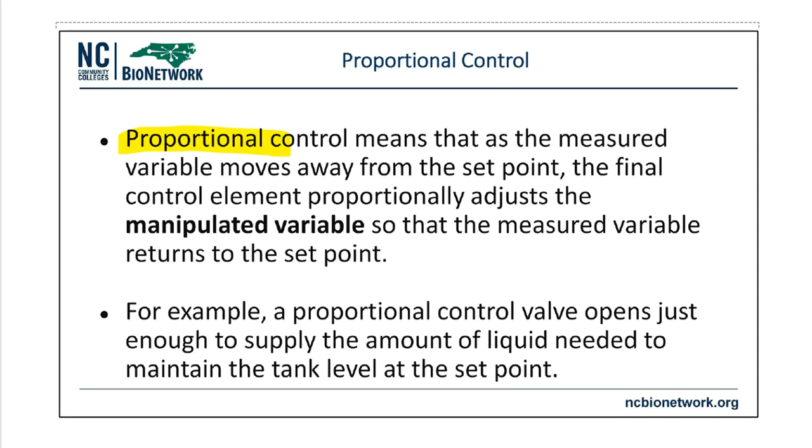So it could just trickle it in, and then it is monitoring what happens in that very, very slow flow. It's going to look at what's happening to the data, and if it sees that it's going above or under again, absolutely, it can just open it up little bits at a time and take care of what it needs. So this is what a proportional control is versus something like an on and off control that you might see at other areas of the plant operating some other pieces of equipment.